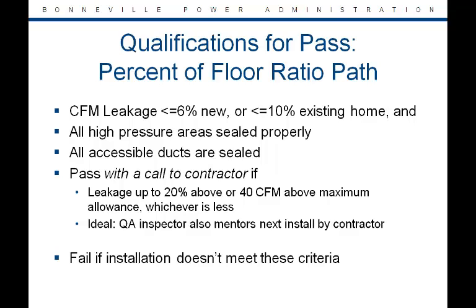Sometimes the test out cannot easily be replicated during the quality assurance inspection. If the CFM leakage is not more than 20% of the expected number, and not more than 40 CFM above the allowable amount, then the job may be passed with a phone call to the contractor. This phone call should happen where the homeowner will not be able to listen in, and will include a discussion with the contractor to understand the circumstances. Ideally, arrangements will be made for the QA inspector to mentor the contractor during their next installation.